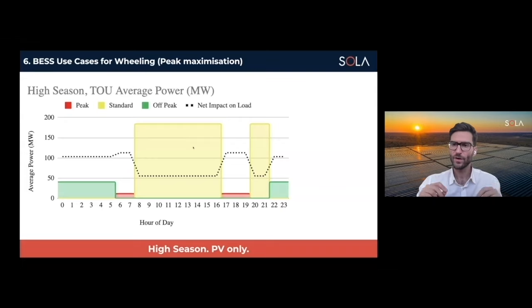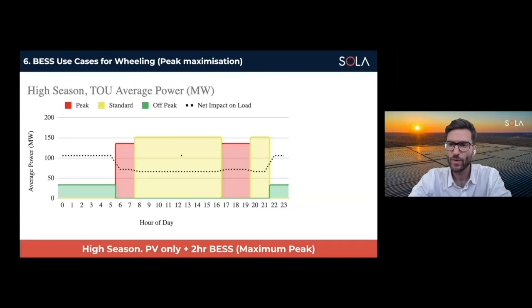that is the energy being put out in standard periods. Eskom's standard periods are predominantly in the day, and that overlaps a lot with the generation of solar power. That's why you see a lot of power coming out of this system in the standard periods. The red is the peak. Solar doesn't generate at night, and those peak periods are in the evenings, and they're actually starting to move further into the evenings in the last tariff adjustment. There's not a lot of peak period generation from a solar generator, for obvious reasons. Now, if we take the same generator and add a 2-hour battery to this, we start to shift from the yellow into the red.